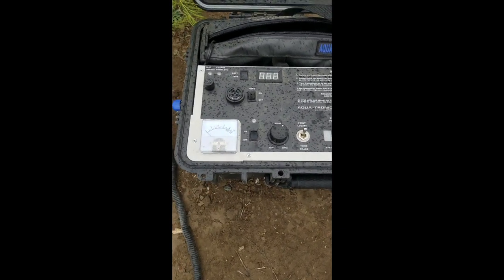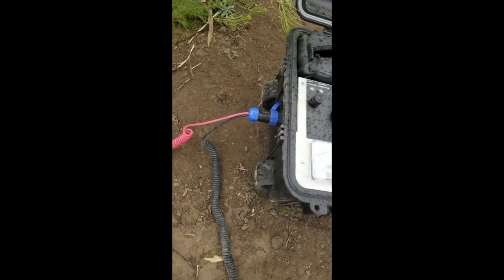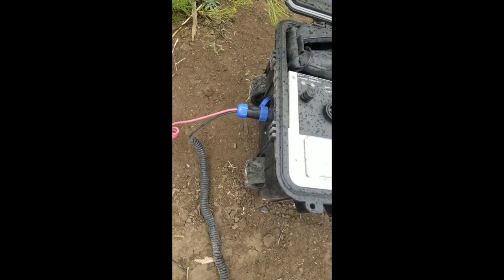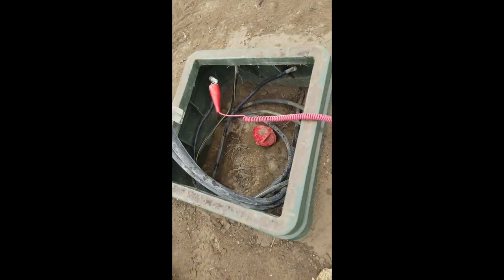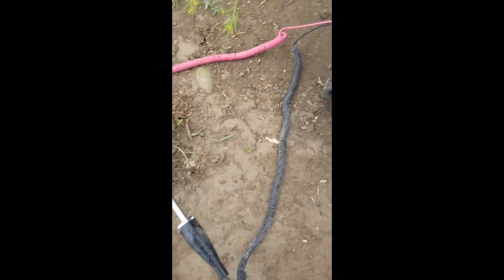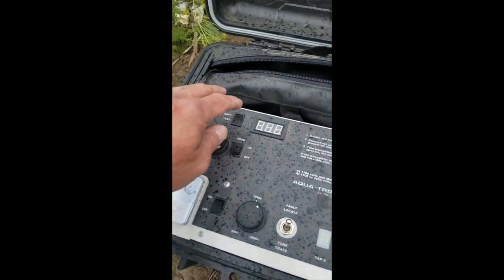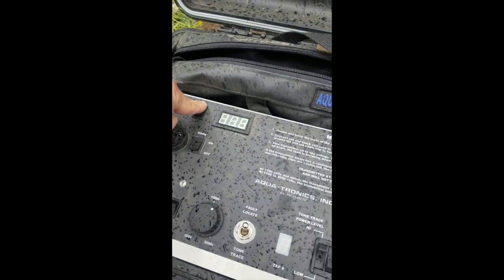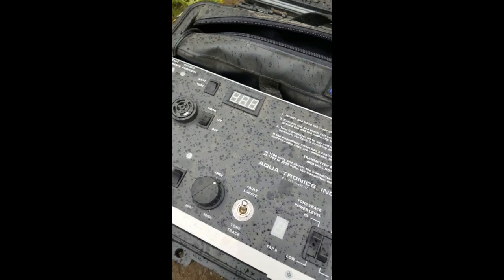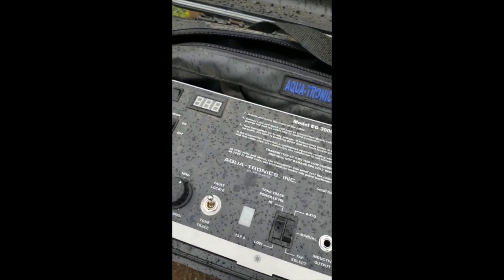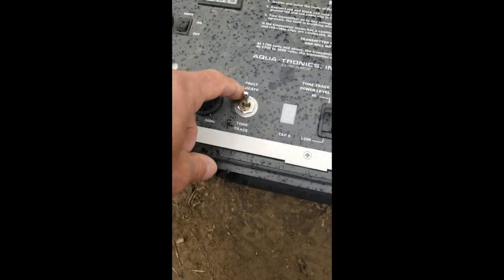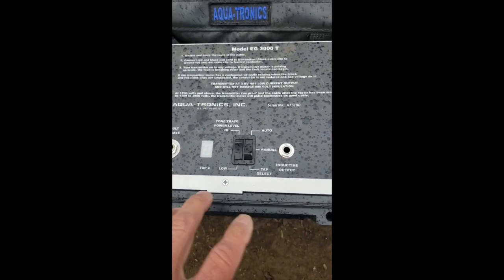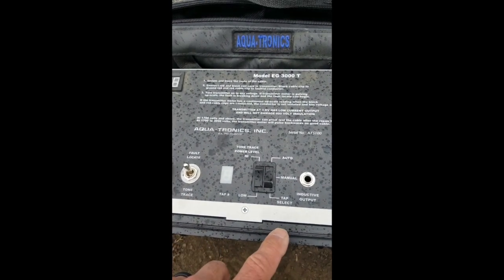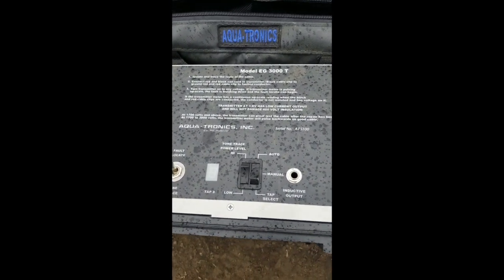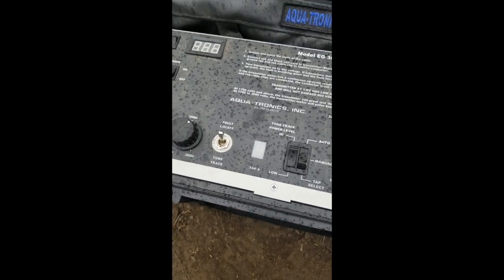You can plug the high voltage cord into the side, the output cables, and go ahead and make your connections to your cables that way. You've got now a new battery test up here. We'll give you battery voltage. Same basic functionality, on off. You've got your voltage control, your fault locate, tone trace switch, and then your cable locating functionality over here. On the right side, you can turn the horn on and off.